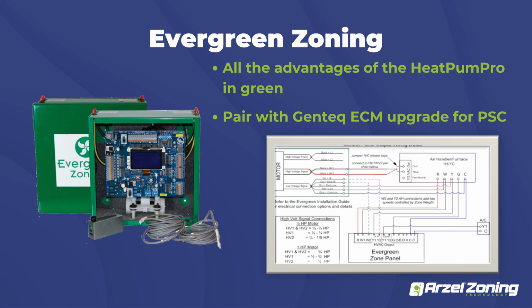This is our Evergreen panel. It's identical to our HeatPumPro. The only difference with this panel is it's shipped with an ECM drop-in replacement motor. So if you guys had a piece of equipment with a regular standard PSC motor, you could purchase this panel. It comes with that ECM motor to pair into their equipment and pairs with the panel very nicely to give them that variable speed motor on an older piece of equipment and still be able to zone it.